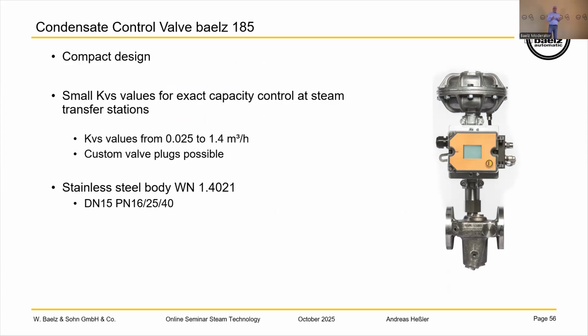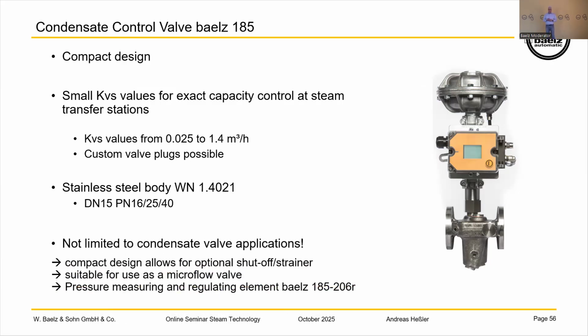If more condensate and more velocity inside the condensate on the heat exchanger are necessary, then we use our control valve 340. It's not limited. We have some special applications. We can mount strainers and shut-off valves inside the valve of the 185. And if we put our element, the 206R, on it, we can also use this as a self-operating control valve.